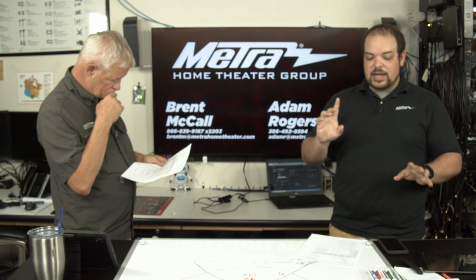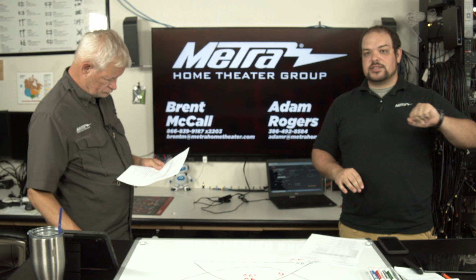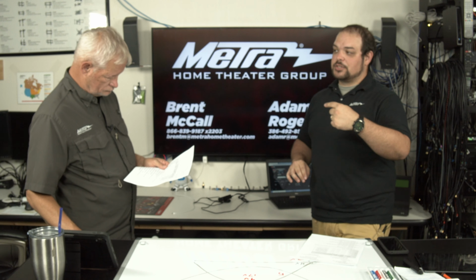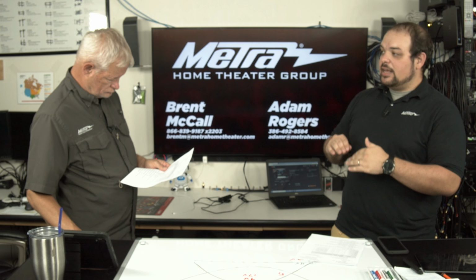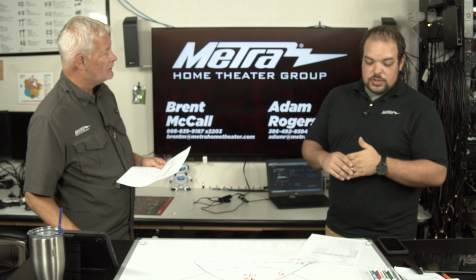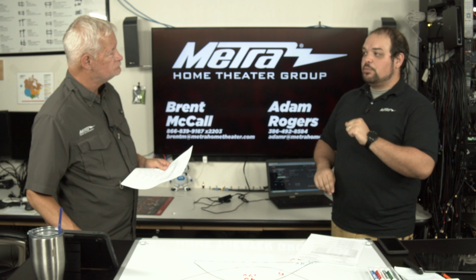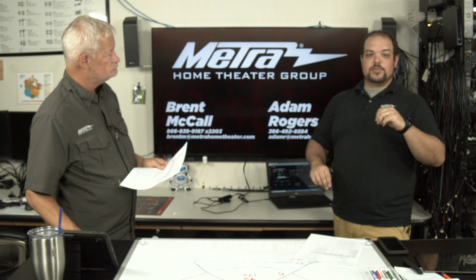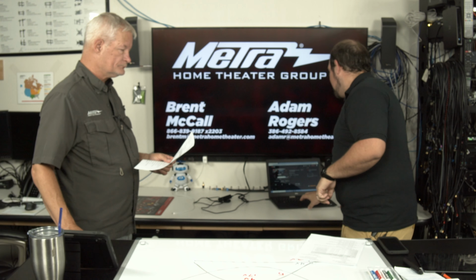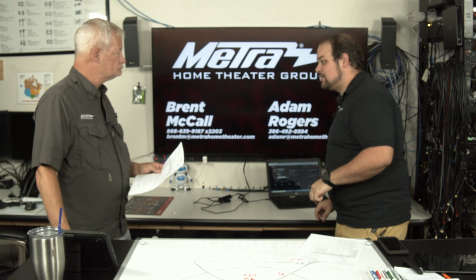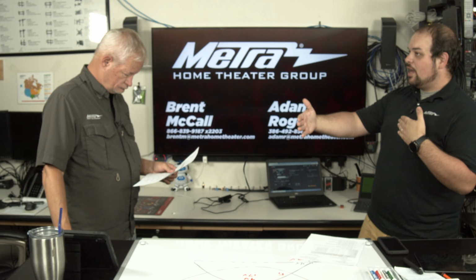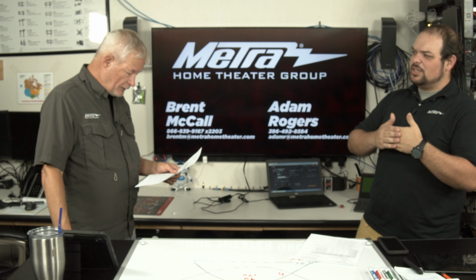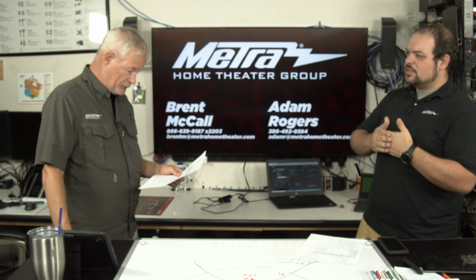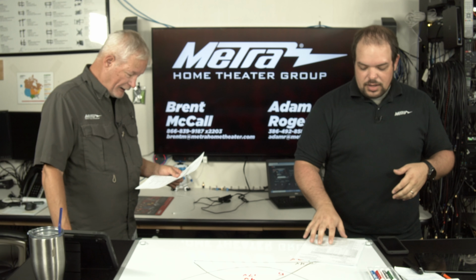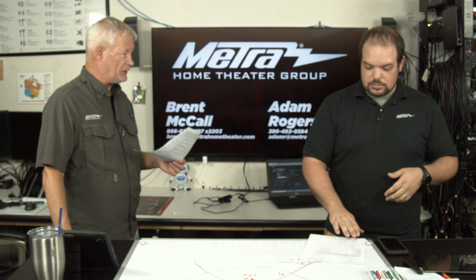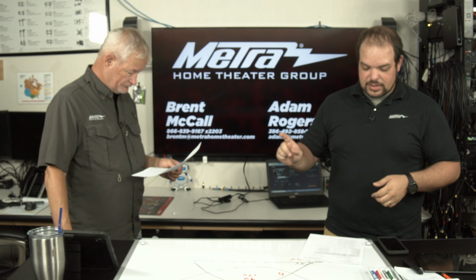Now, that doesn't mean we have only 12.95 watts coming out of the PSE, the power supplying equipment. That can increase because of distance, all the way up to 15.4 watts. So there's a lot of headroom. And actually, the headroom increases as you go up. Is it exponentially? No, it's not exponentially, but it does increase, possibly substantially in some cases. Correct, that's probably the better way to look at it.